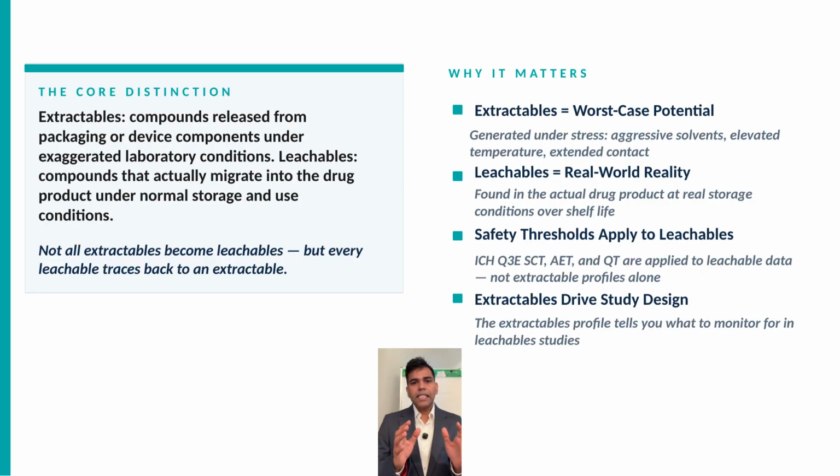So what exactly is the difference between extractables and leachables? These terms are often used interchangeably, but they describe two different things. Extractables are compounds released from packaging or device components under exaggerated laboratory conditions: aggressive solvents, elevated temperature, extended contact times. They represent worst case potential.